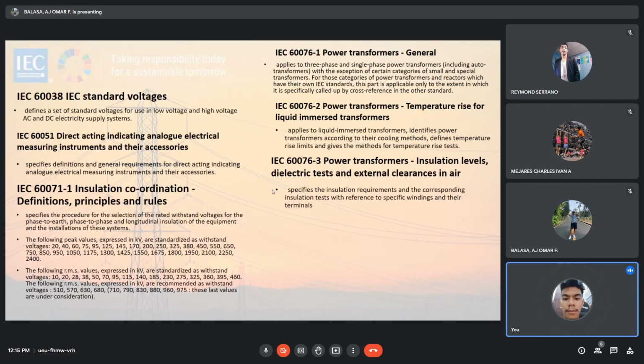So here, it mentions the altitude or height above sea level of power transformers. Above sea level, it should not exceed 1,000 meters or 3,300 feet. It also covers the temperature of ambient air and cooling medium. The temperature of ambient air should not go below minus 25 degrees Celsius and should not go above 40 degrees Celsius. For water-cooled transformers, the temperature of cooling water at the inlet should not exceed 25 degrees Celsius.